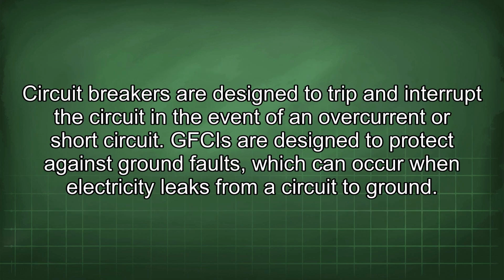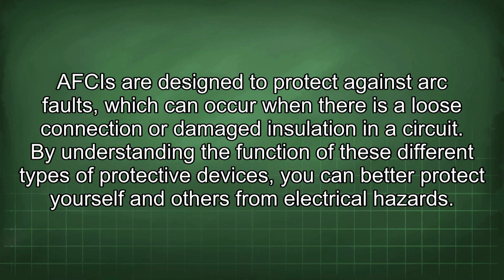Circuit breakers are designed to trip and interrupt the circuit in the event of an overcurrent or short circuit. GFCIs are designed to protect against ground faults, which can occur when electricity leaks from a circuit to ground. AFCIs are designed to protect against arc faults, which can occur when there is a loose connection or damaged insulation in a circuit. By understanding the function of these different types of protective devices, you can better protect yourself and others from electrical hazards.